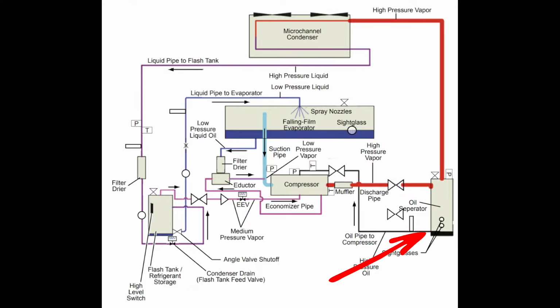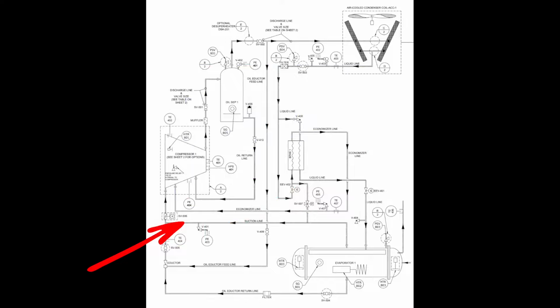And we have our oil separator, oil input circuit, all that relatively the same. Well, we do have an EXV on the leaving side of the flash tank that was metering flow. This is how we controlled flow coming from the flash tank to the compressor. All right. Now, let's go look at a series B. We're going to see some significant differences here.